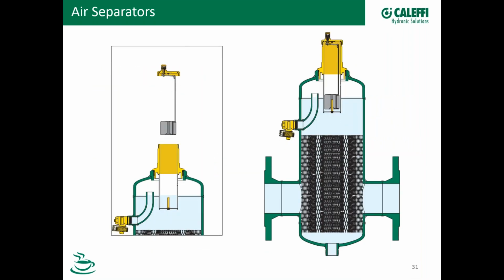Here's a nice cutaway of our commercial model. Now you can see the coalescing element in there. And what you'll notice too is on this one, the air vent has a really long float chamber. What that does is it prevents debris from getting into the vent mechanism. And the picture on the left shows you how you can pull the whole thing out and clean it.